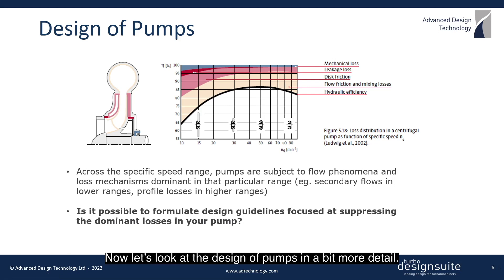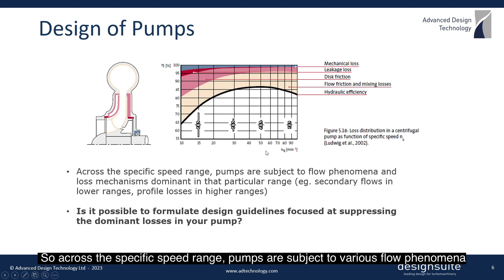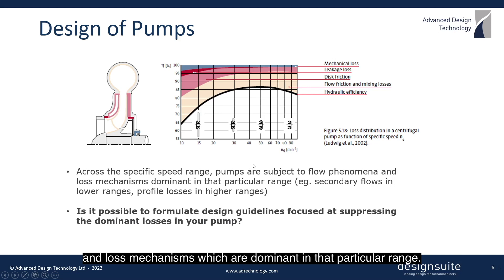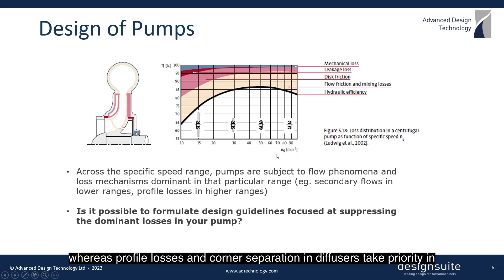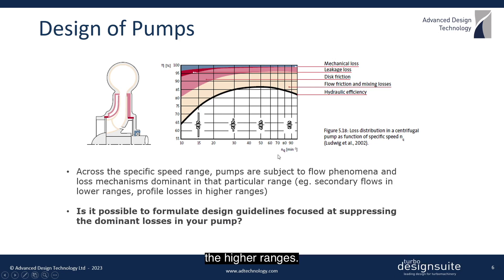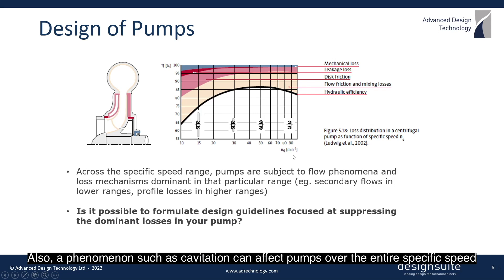Let's look at the design of pumps in a bit more detail. Across the specific speed range, pumps are subject to various flow phenomena and loss mechanisms which are dominant in that particular range. As you can see in this specific speed chart, leakage and secondary flow effects are more dominant in the lower ranges, whereas profile losses and corner separation in diffusers will take priority in the higher ranges.